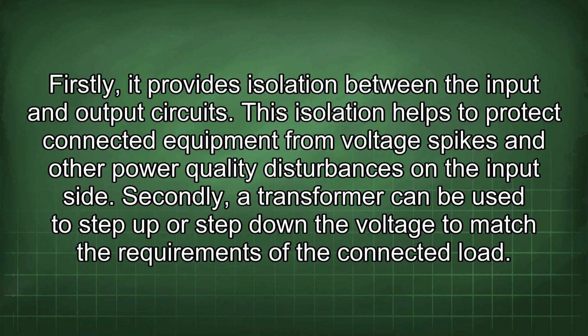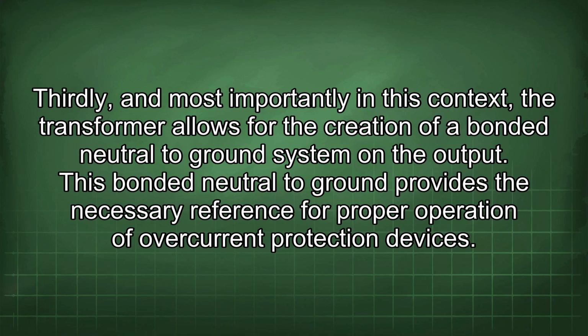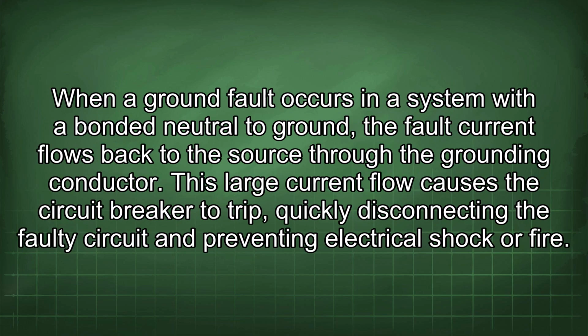Secondly, a transformer can be used to step up or step down the voltage to match the requirements of the connected load. Thirdly, and most importantly in this context, the transformer allows for the creation of a bonded neutral to ground system on the output. This bonded neutral to ground provides the necessary reference for proper operation of overcurrent protection devices. When a ground fault occurs in a system with a bonded neutral to ground, the fault current flows back to the source through the grounding conductor. This large current flow causes the circuit breaker to trip, quickly disconnecting the faulty circuit and preventing electrical shock or fire.